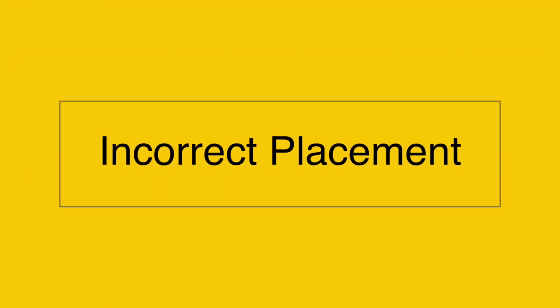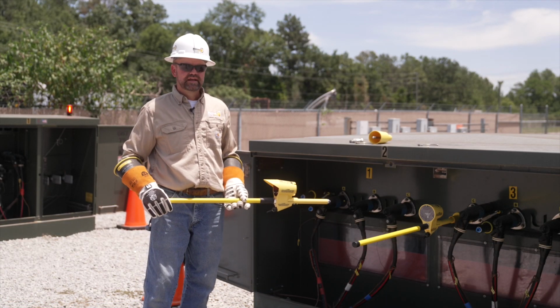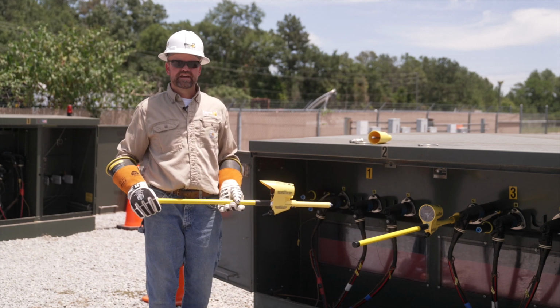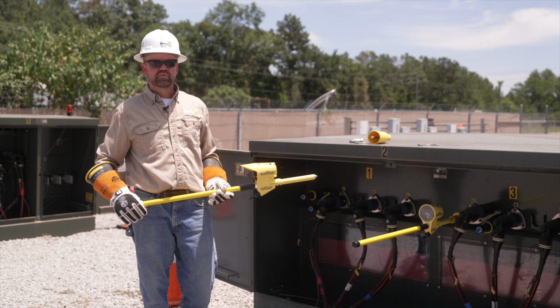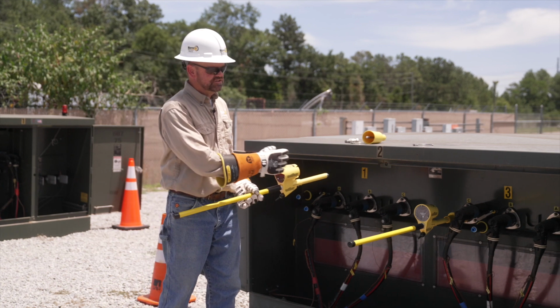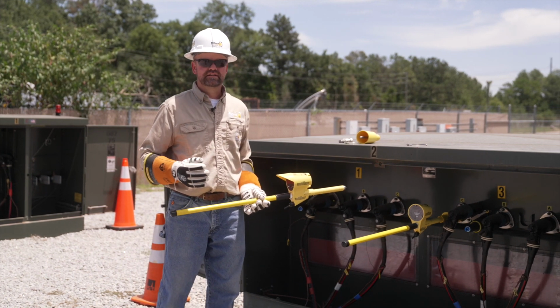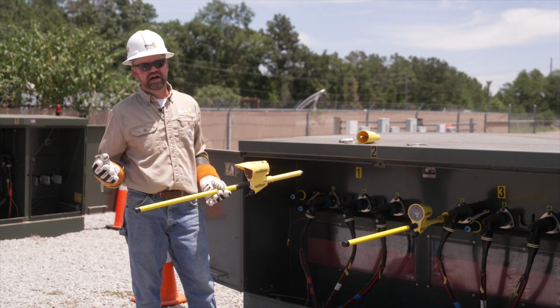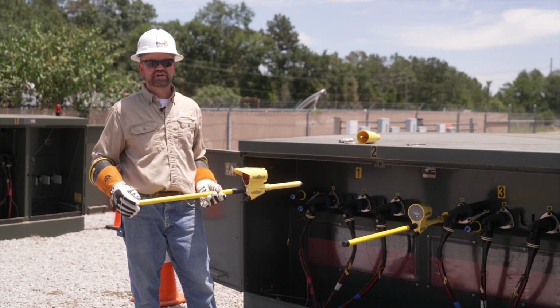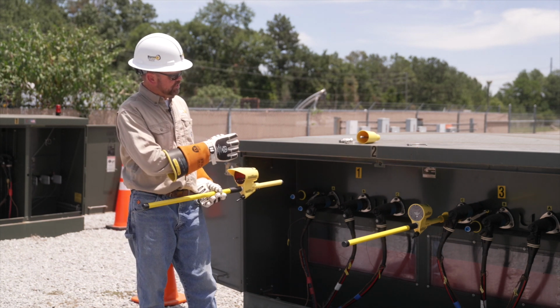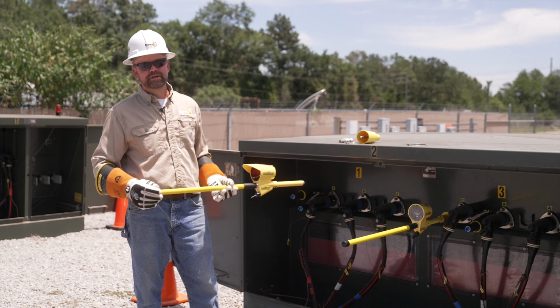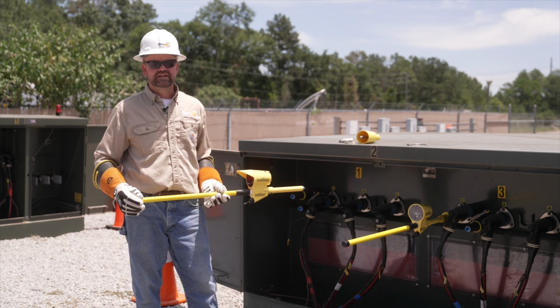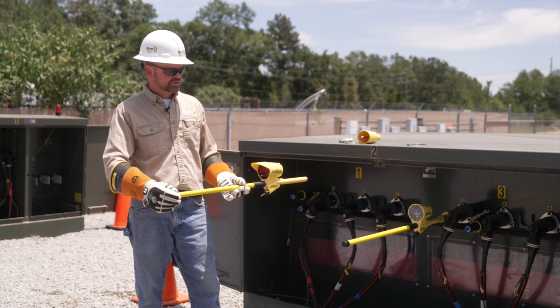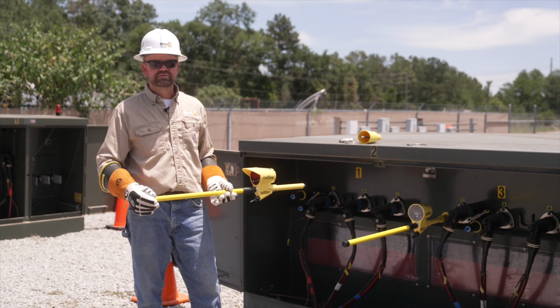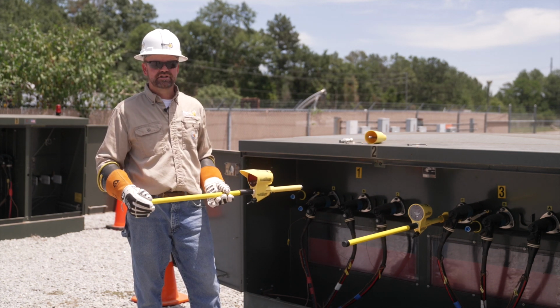So they're in phase. Okay, I'm going to use this opportunity to demonstrate what not to do when you're phasing with these devices. In other words, you don't want the housings of these devices to be within 2 feet if you can help it. Sometimes, obviously, you can't always control the situation you're in, but this situation right here forces me to put the housings within 2 feet. So I can just use the meter probe angle to adjust and make sure I get a good reading.